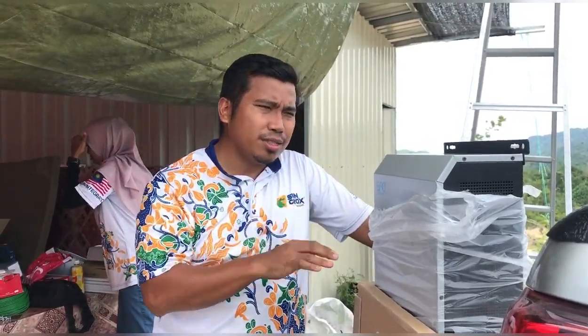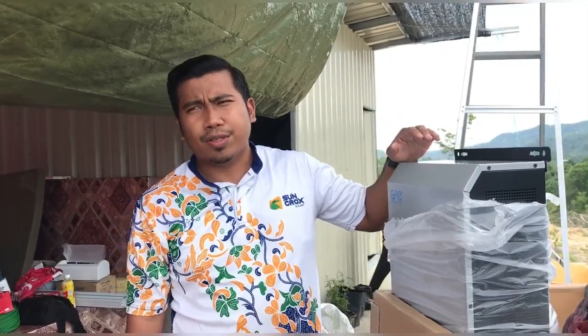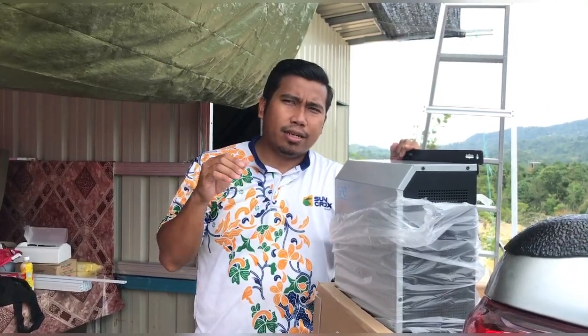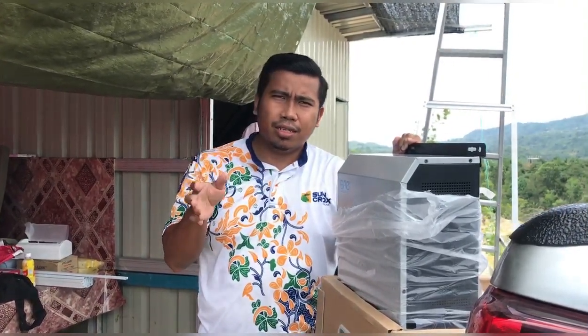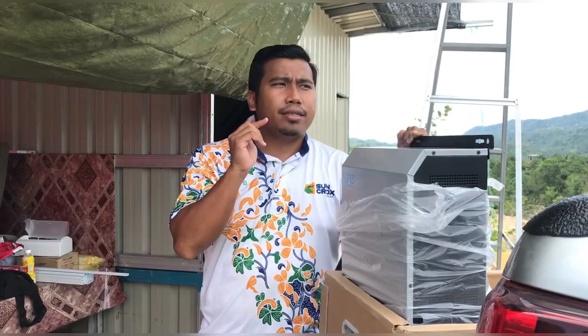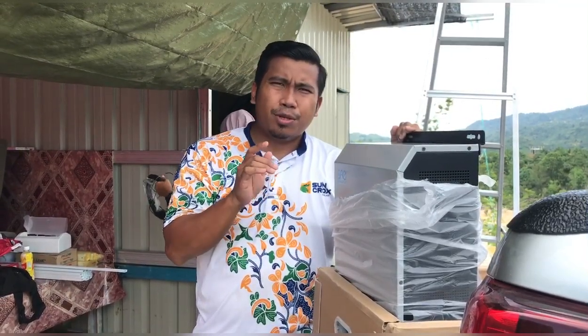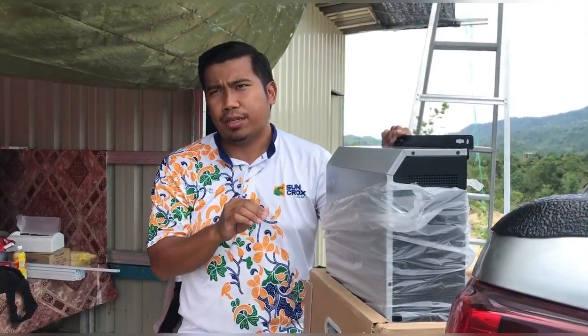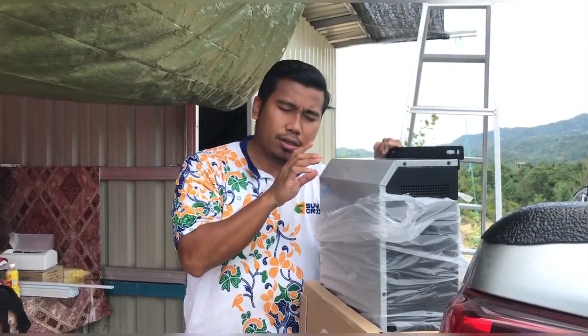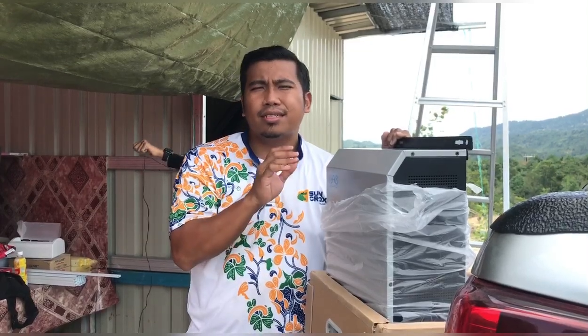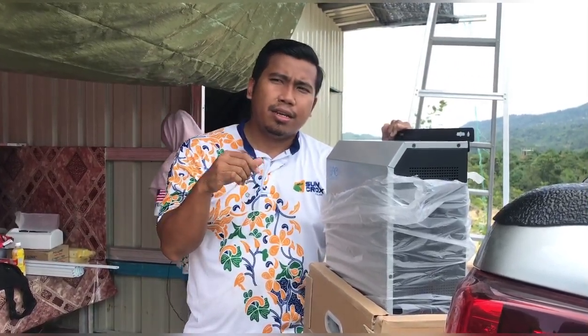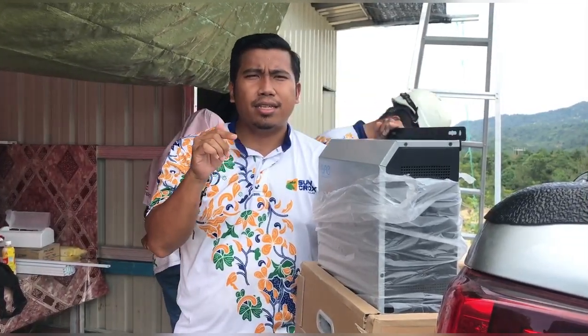Alright, so the installation for this system is using hybrid inverter. We are using 3 kilowatt low frequency hybrid inverter. Okay, let me give you a brief setup of this place lah. It's a small farm. The electricity will be used for basic lighting, fans, charging gadgets, and the owner wants to use water pump. Okay, due to the water pump requirement, we must use low frequency inverter to sustain the surge from the AC pump, and the owner wants to use AC pump.